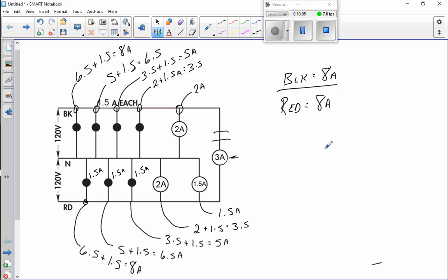So one more time, because we took out this load that was shared across the two, we have simply dropped our load 3 amps from 11 amps down to 8. We still do not have an unbalanced load, so our neutral is going to be 0 amps once again. Hopefully that's clear to everybody. So this would be question number 9, 10, and 11.